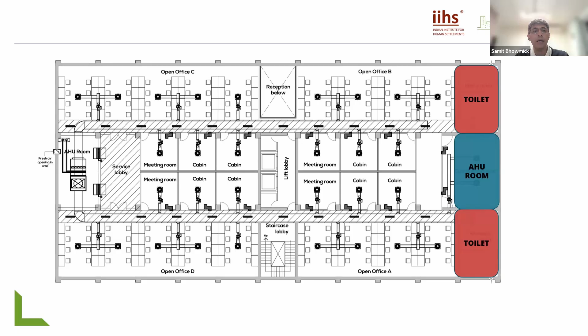Along with that, the location of these units - I can't undermine the importance of this. In every project, the first thing we look at is how we're locating the outdoor air intake, the fresh air intake, and the exhaust. This is extremely key because only fresh air is going to dilute and make sure the space's IAQ is better. You cannot do it by any other means.